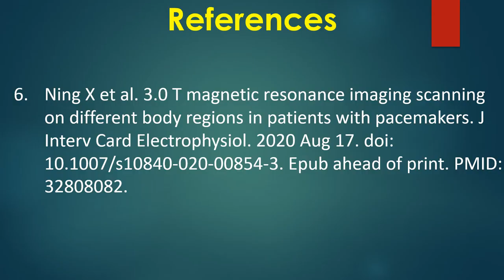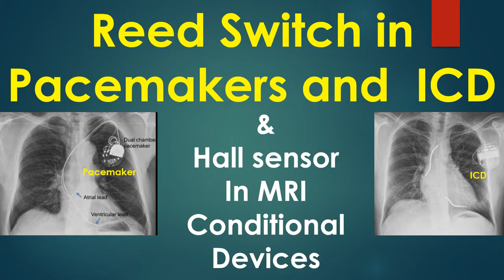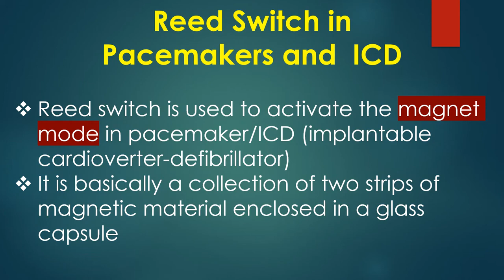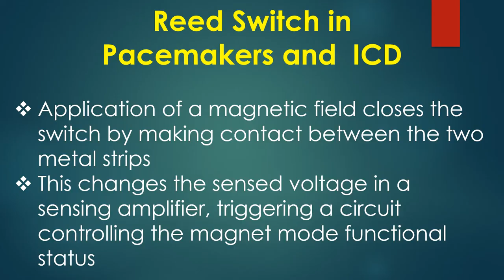This discussion is on reed switch in pacemakers and implantable cardioverter defibrillators. Includes a mention on its replacement by Hall sensor in MRI conditional devices. Reed switch is used to activate the magnet mode in pacemaker or implantable cardioverter defibrillator. It is basically a collection of 2 strips of magnetic material enclosed in a glass capsule. Application of a magnetic field closes the reed switch by making contact between 2 metal strips. This changes the sensed voltage in a sensing amplifier, triggering a circuit controlling the magnet mode functional status.